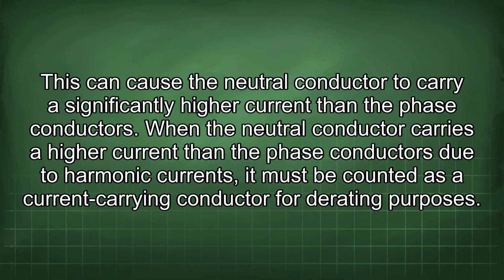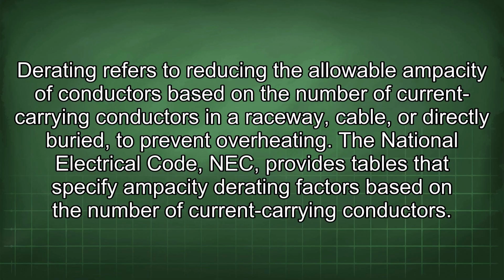When the neutral conductor carries a higher current than the phase conductors due to harmonic currents, it must be counted as a current-carrying conductor for derating purposes. Derating refers to reducing the allowable ampacity of conductors based on the number of current-carrying conductors in a raceway, cable, or directly buried, to prevent overheating. The National Electrical Code, NEC, provides tables that specify ampacity derating factors based on the number of current-carrying conductors.